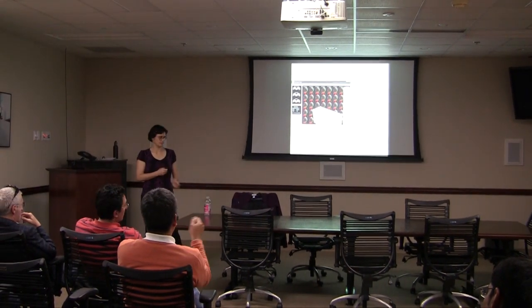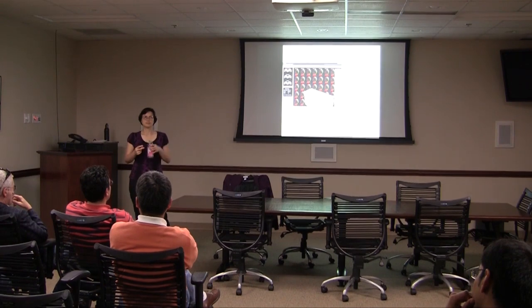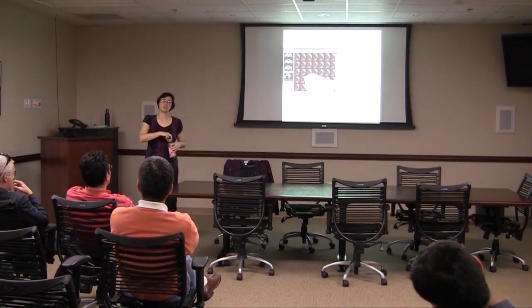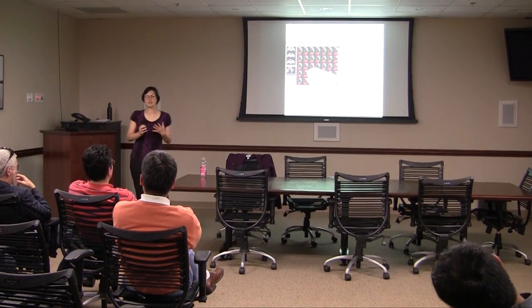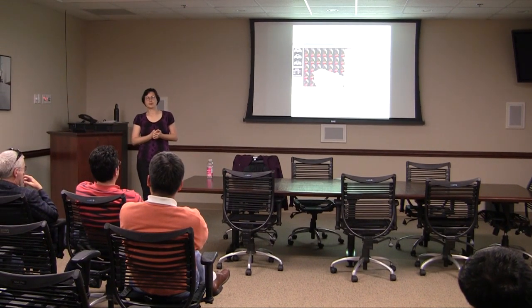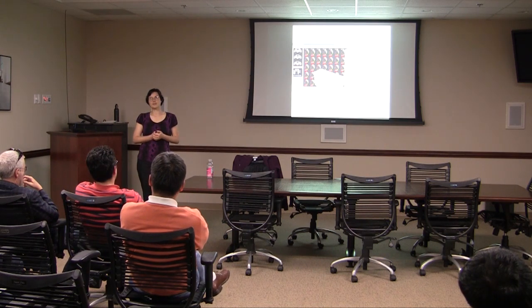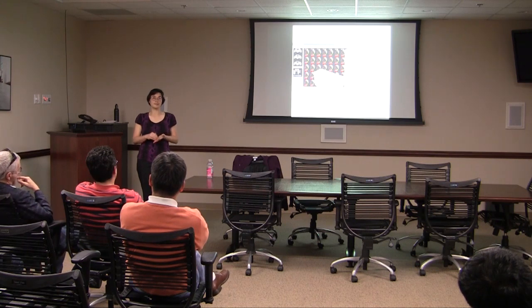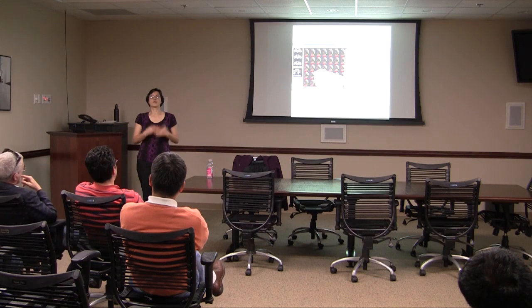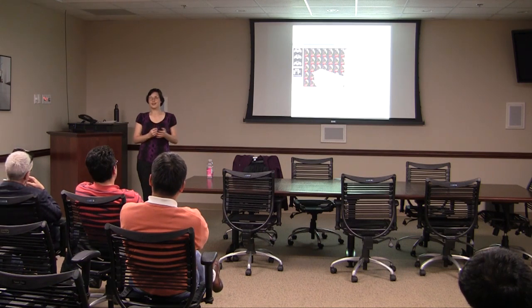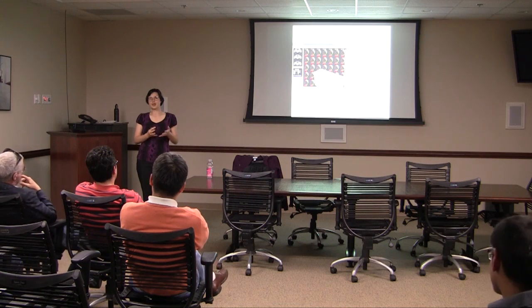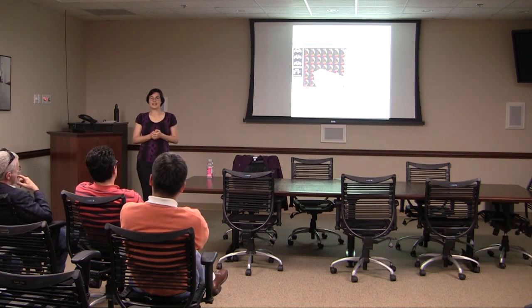Out of curiosity, what percentage of power is consumed by the processors? It depends on the server. Servers with less memory have a higher percent of power due to the processor, about 40% maybe. Servers with a lot of memory, like an Oracle database type server, see the processor fraction go down, but the fraction of power due to memory goes up, and due to fan also goes up—so the more memory you have, the more fan speed you need. This seems counterintuitive, but memory is always on, and memory's critical temperature is actually lower than the processor's.